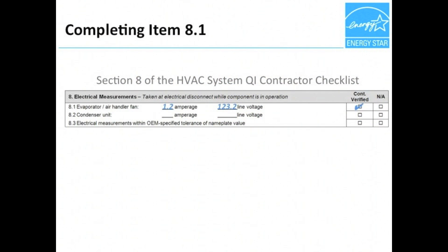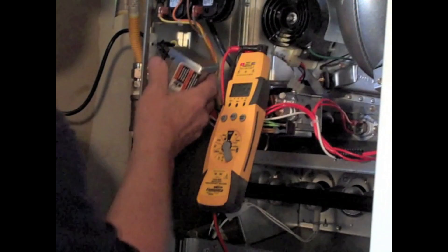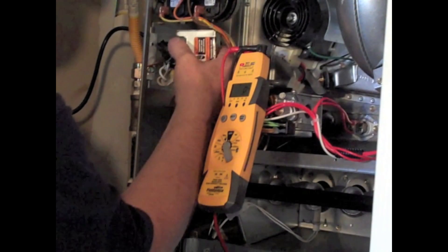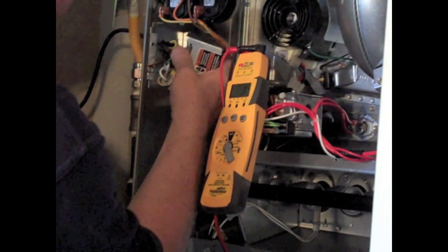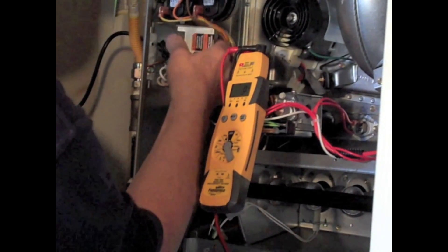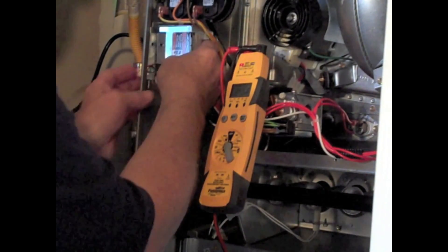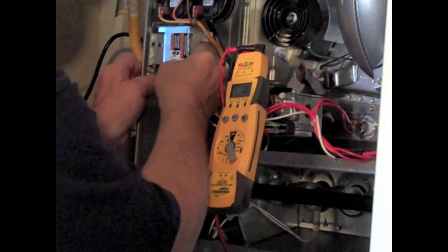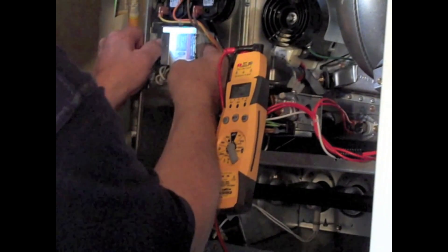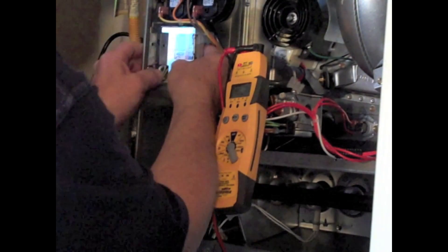Now Rob can complete item 8.1 of the checklist. He records the current and voltage values that were measured at the evaporator air handler fan. Since we are already inside the air handler, we could do a quick check for one of the values needed for Section 6, refrigerant tests — that is the return air wet bulb temperature for item 6.2.